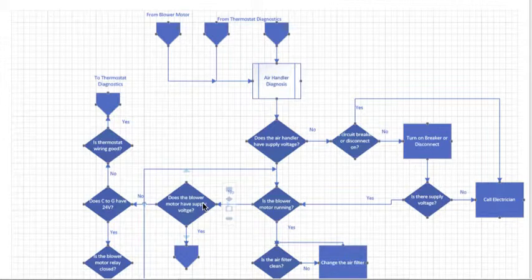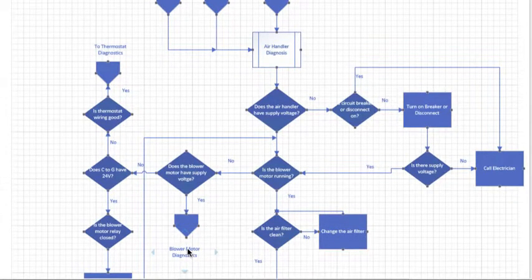If the blower motor has supply voltage and is not running, we're going to have you jump over to blower motor diagnostics. We'll get into that in a little bit. But let's go under the assumption the blower motor does not have supply voltage. Check the terminal strip between C and G. Do you have 24 volts? Those are your wires coming from the thermostat. So if our thermostat is set to fan on, and I do not have 24 volts from C and G, we have to take a closer look.